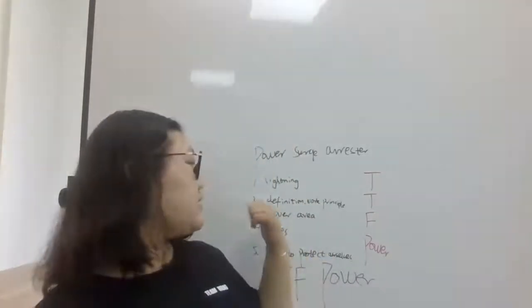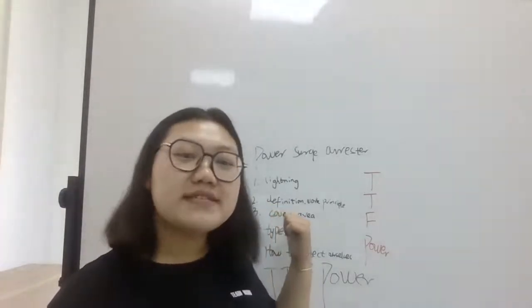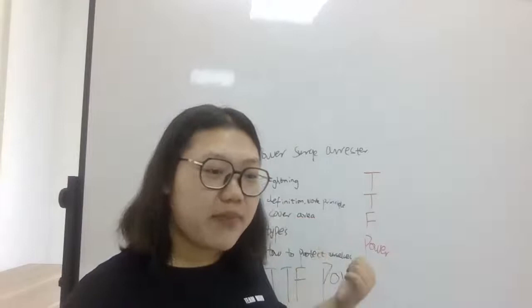That moves us to our third item here, the cover area. What is the approximate area covered by a surge arrestor? Let's talk about it. The radius covered depends on several factors, including the type of head, the type of material, and the height of the surge arrestor, which is generally located in high areas of large buildings to increase coverage. The head, among other factors, can cover a radius of up to 1 kilometer.